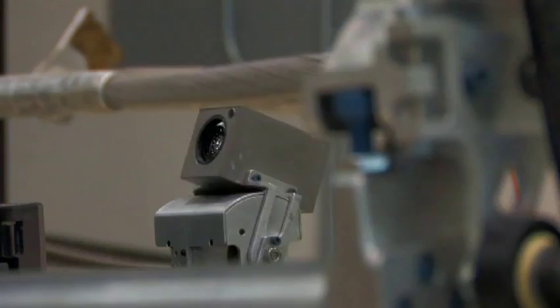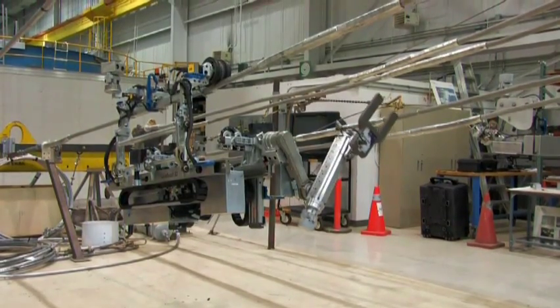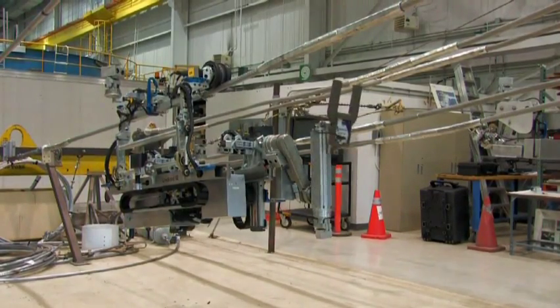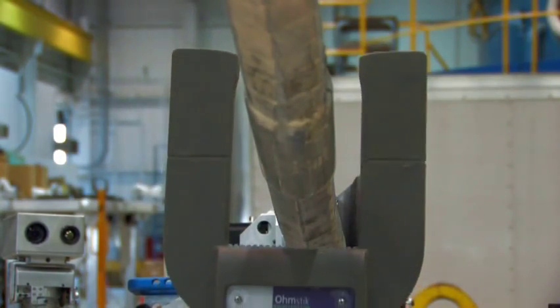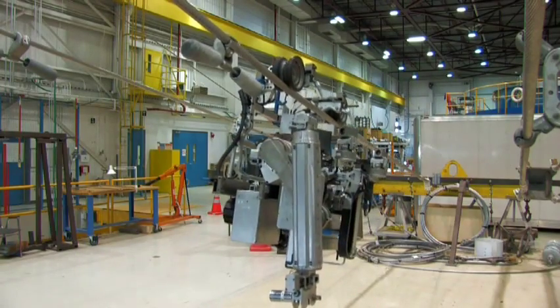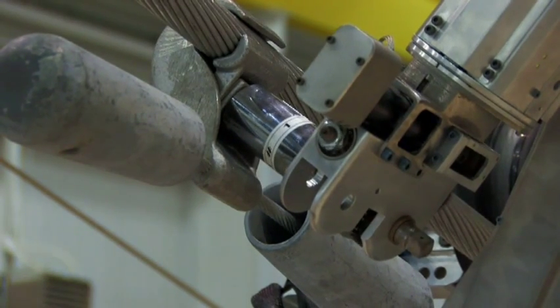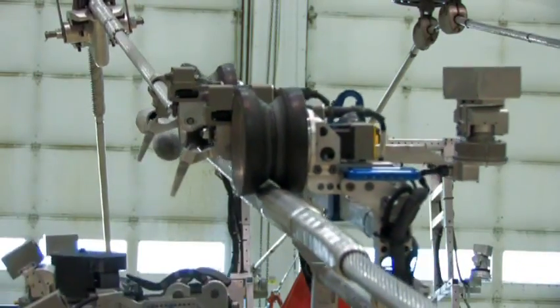What it allows you to do is to be on the conductor, providing exceptional points of view. It allows you to measure things like the electrical resistance of the splices. It allows you to bring sensors very close to the component. It allows you to intervene on components also — you can repair a conductor, you can unscrew bolted assemblies. It allows you to work away from the dangers represented by energized components, but also damaged structures like broken strands on conductors or overhead ground wires.